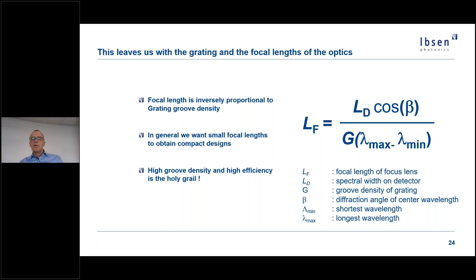As we discussed in the previous slides, the detector length and wavelength range are given by your application, so the only parameter we can work with is the grating groove density. In general, we want the device to be as compact as possible, meaning the focal length should be short. So we want a grating with a groove density G as high as possible. At the same time, we of course also want the grating to provide a high efficiency so that we don't lose too many of the precious Raman scattered photons.